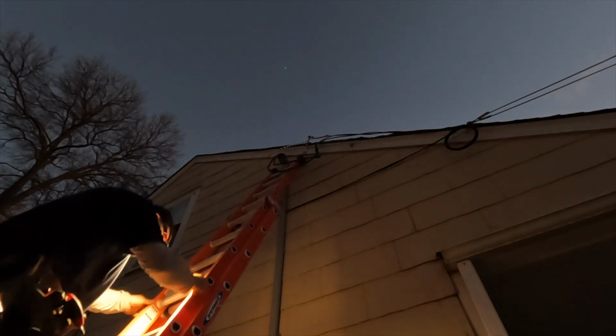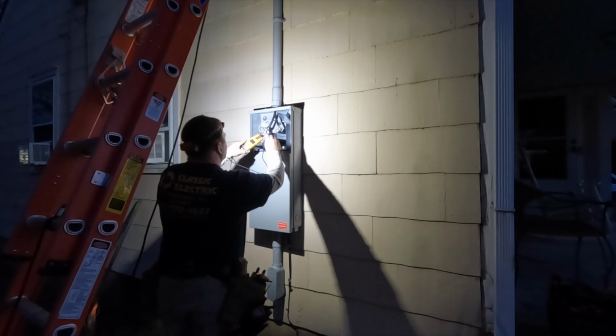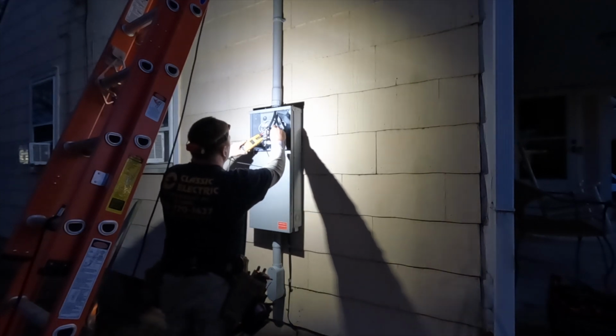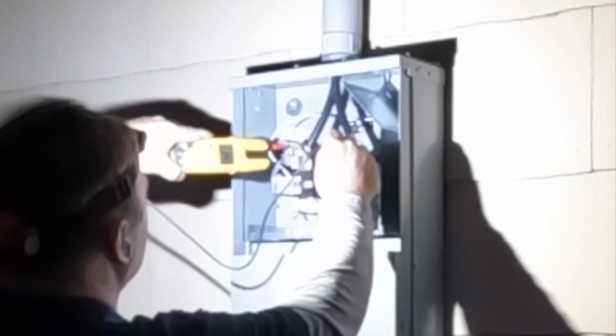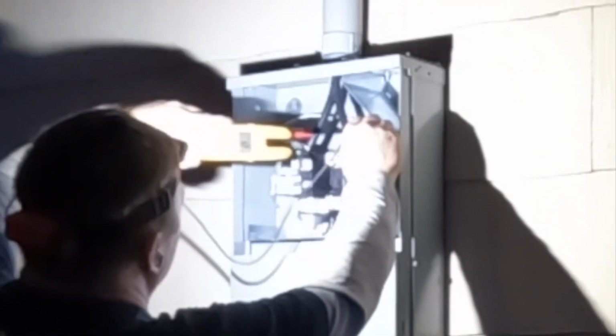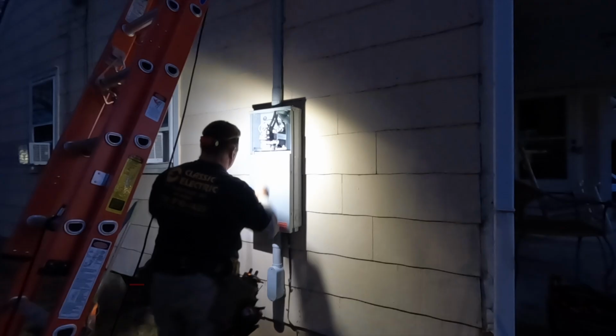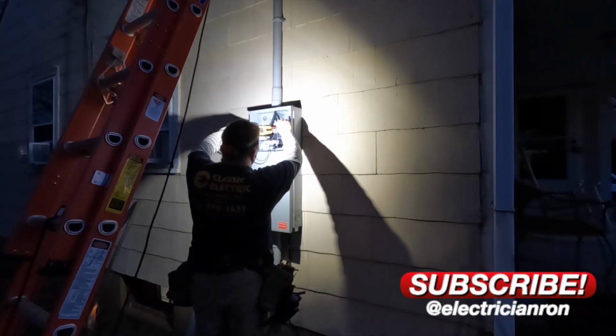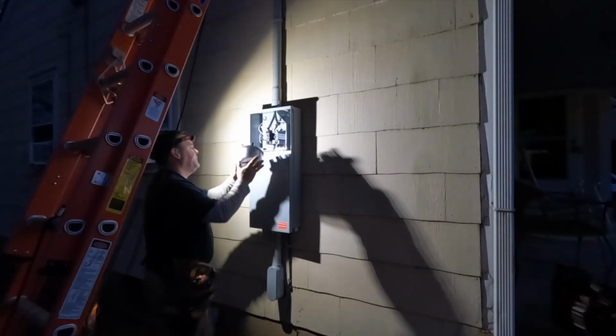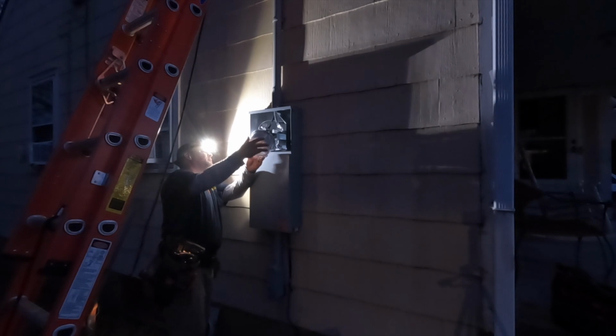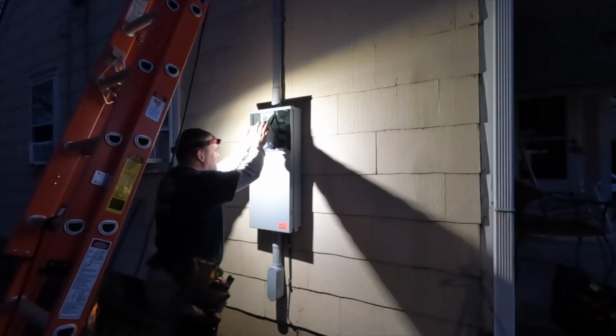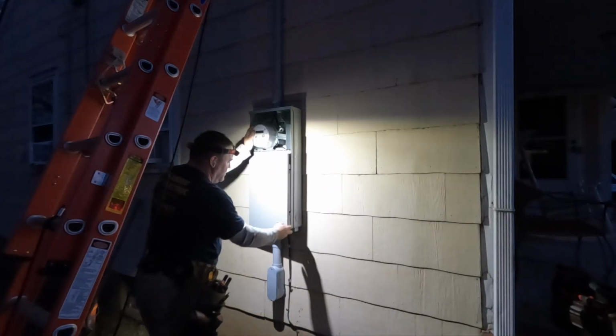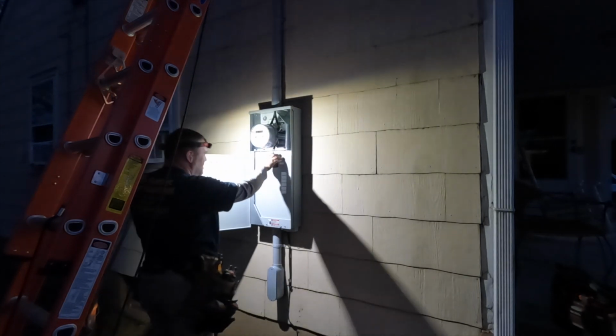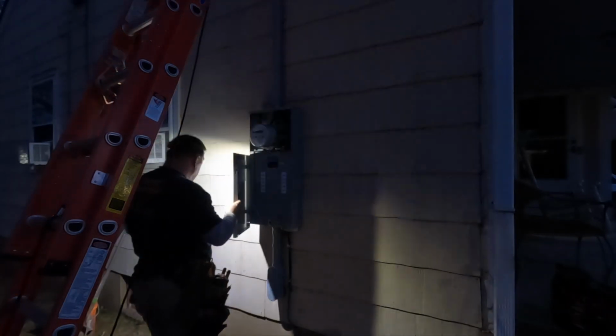But once I get down off the ladder from splicing in, from cutting back in, we're going to take my voltage testers. I should have 240 volts between L1 and L2, and 120 volts between each of the legs to neutral. Once I know I have that, I've already checked for faults, but I'm going to check it again here. Just make sure I got no short circuits or any continuity between any of my lugs. And then I'm going to install the meter. And once we install the meter, I'll turn on that main breaker inside the enclosure, and then I'll go downstairs to the panel and turn on each of the individual circuit breakers, which will restore power back to the house.